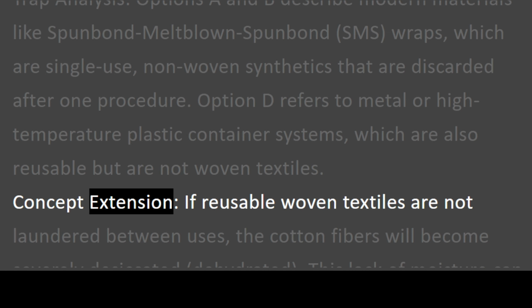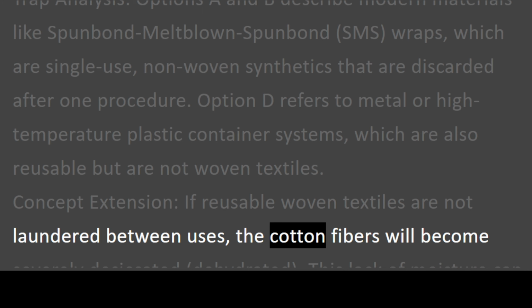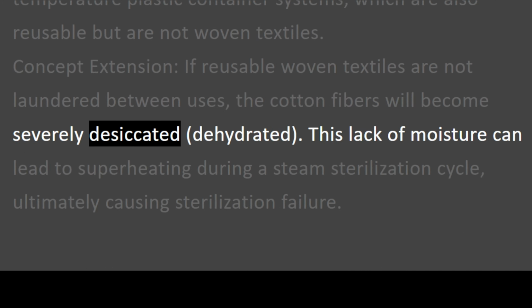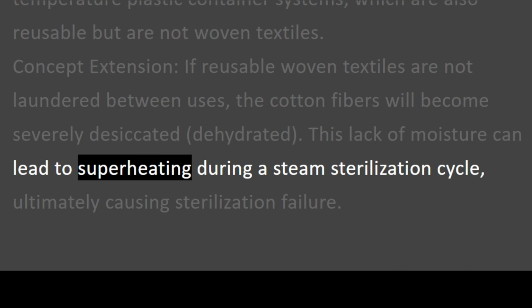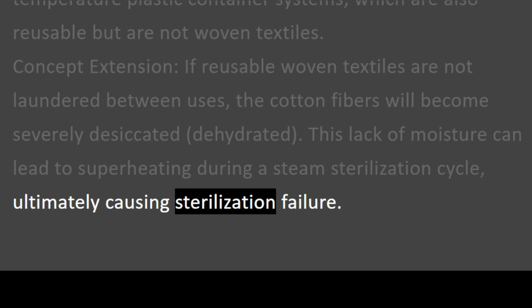Concept extension: if reusable woven textiles are not laundered between uses, the cotton fibers will become severely desiccated, dehydrated. This lack of moisture can lead to superheating during a steam sterilization cycle, ultimately causing sterilization failure.